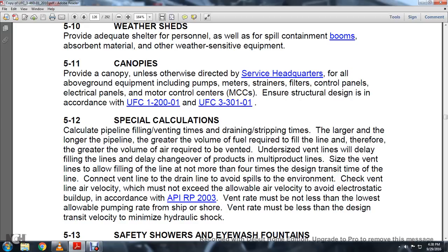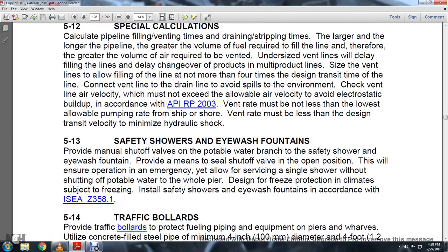Size vents and lines allowing the line to be vented at not more than 4 times the transit time of the line, conducting the vent line with the drain line valve to avoid spills in the environment. Check the air velocity of the vent line, which must not exceed the allowable air velocity, to avoid electrostatic buildup in accordance with API RP 2003. The vent rate must not be less than the lowest allowable pumping rate from ship or shore. The vent rate must be less than the design transit velocity, minimizing hydraulic shock.